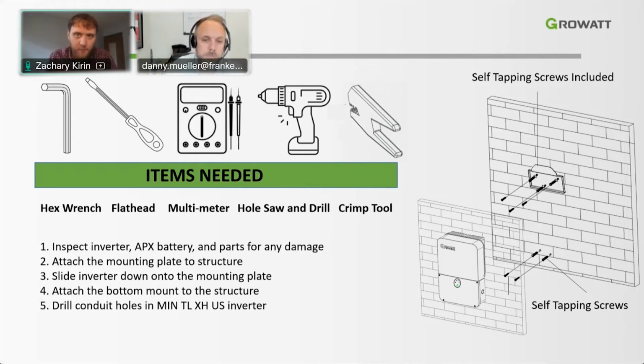So the most important part is to inspect the products that you have in front of you right out of the box. First, for the MIN inverter, you will attach the mounting plate to the structure. And this is done utilizing our drill. You're going to attach the mounting bracket here to the wall using the screws that are included. And then you can slide the inverter right down onto the mounting plate. It's as simple as only 5 screws to install this inverter. The 3 for the mounting bracket, then the inverter is slid down onto the mounting bracket, and then the bottom end of the inverter has 2 self-tapping areas for screws. We'll include those screws with the inverter, and you'll be able to install the bottom half to the wall as well. So it's really that simple.